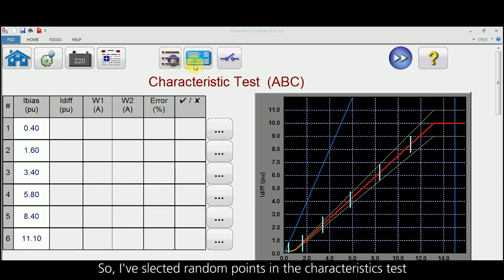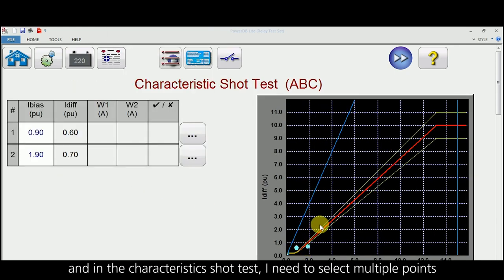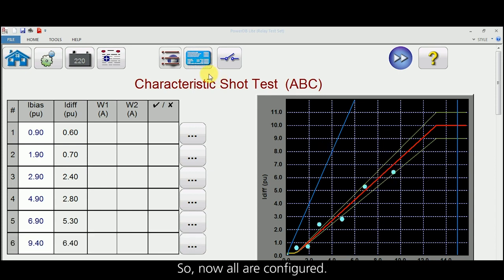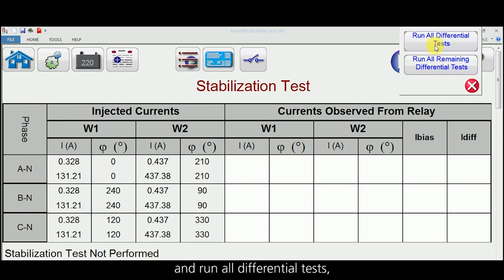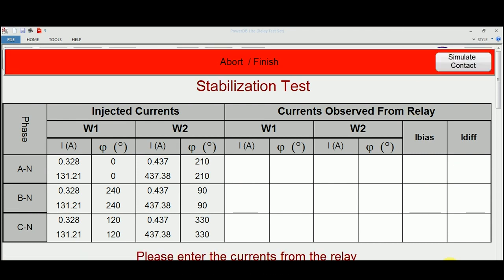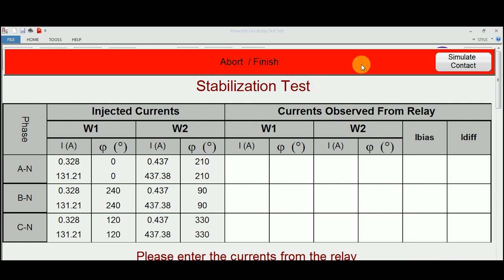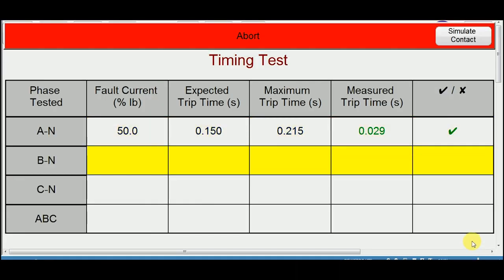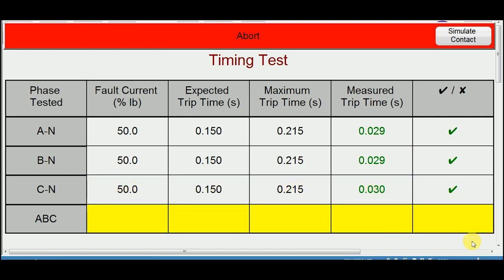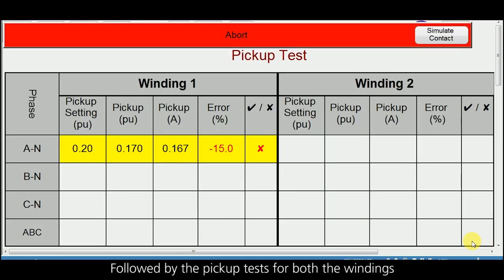To do this I need to select multiple points in the characteristics. I have selected random points in the characteristics test, and in the characteristic shot test I need to select multiple points. Now all are configured. Let me run all differential tests. We can see that the relay has not tripped, which confirms the relay is stable.